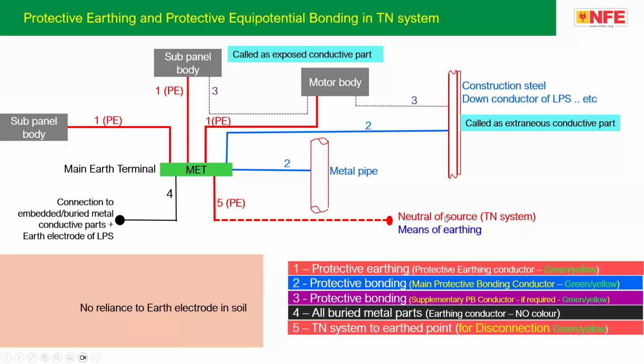So in a TN system, legally we are supposed to follow the TN system in India. The earthing is made in this typical fashion. This is defined in the CEA regulation 2023. It is also defined in CEA regulation number 43, sub-regulation 5. I will show you this in just a minute. So fundamentally, a lot of change happened after 2020, especially in the CEA regulation as well as in upcoming documents such as the NEC.